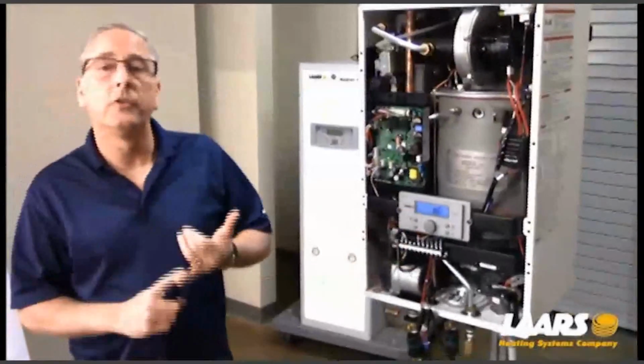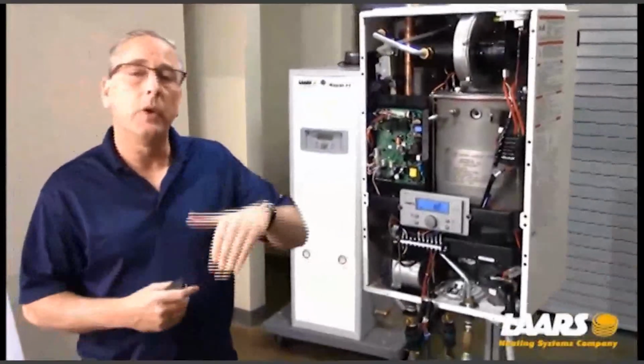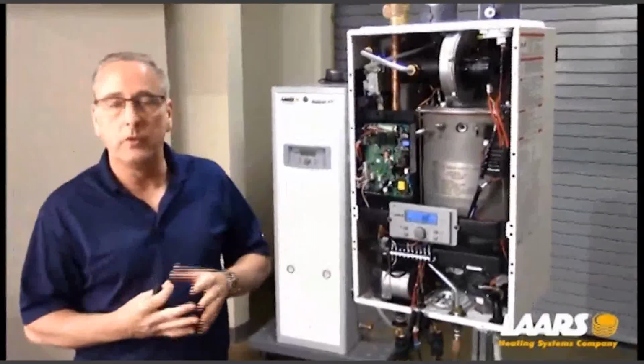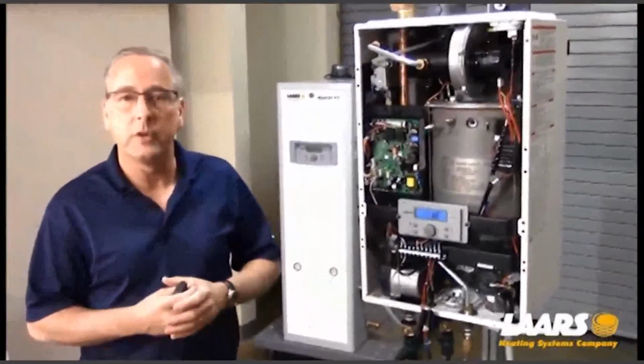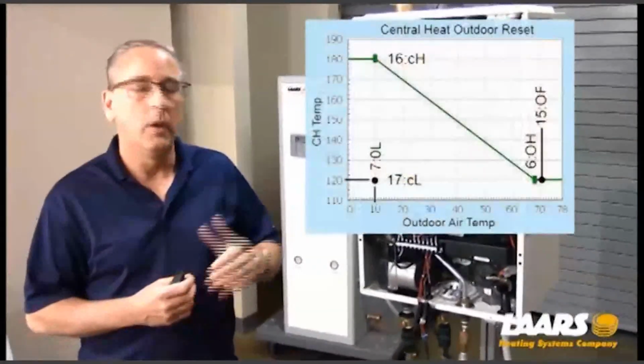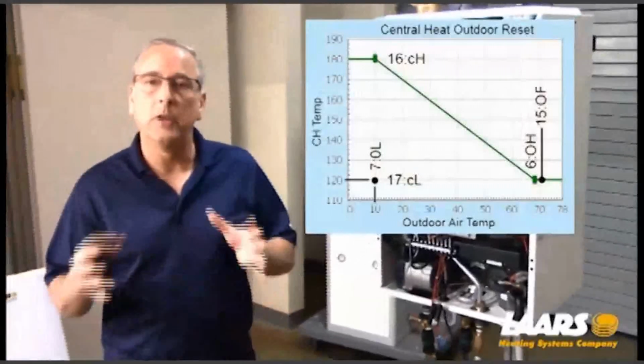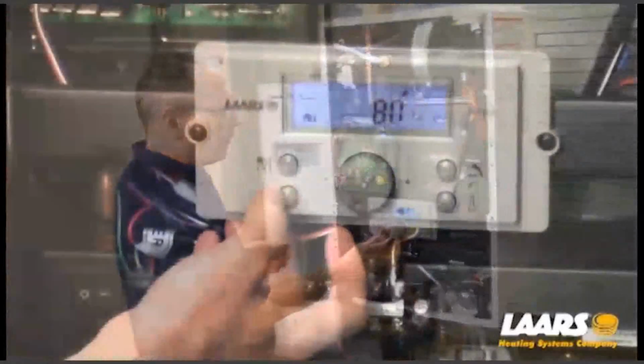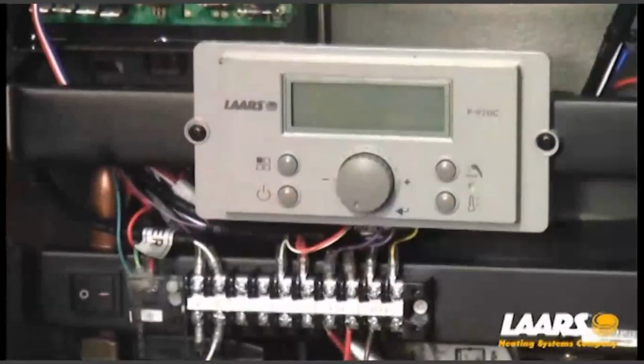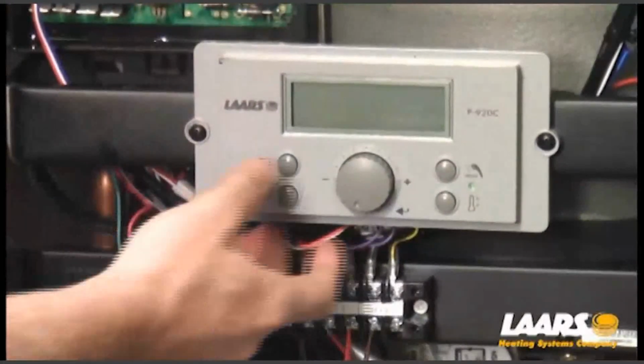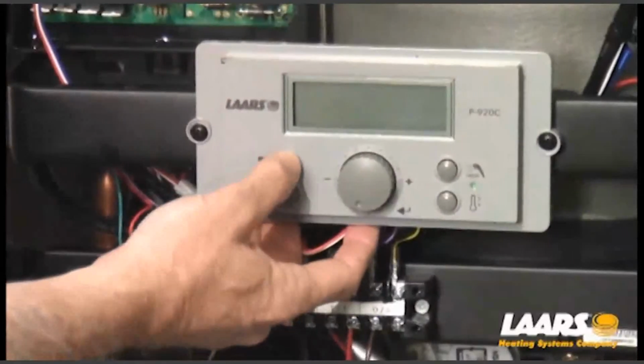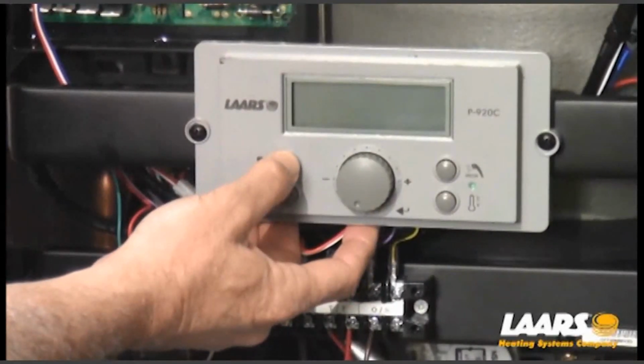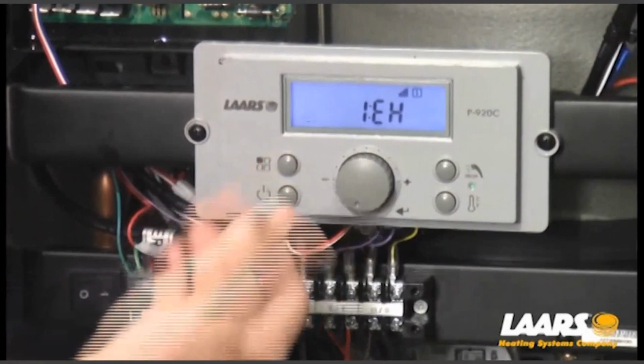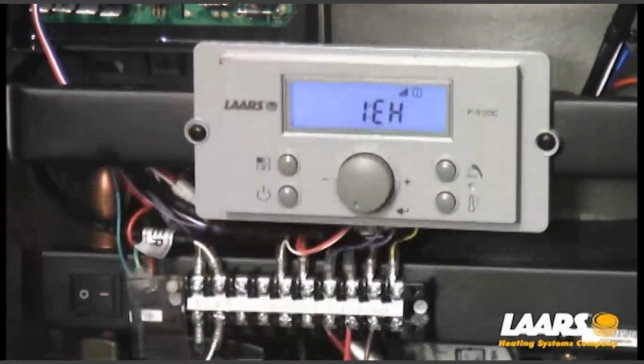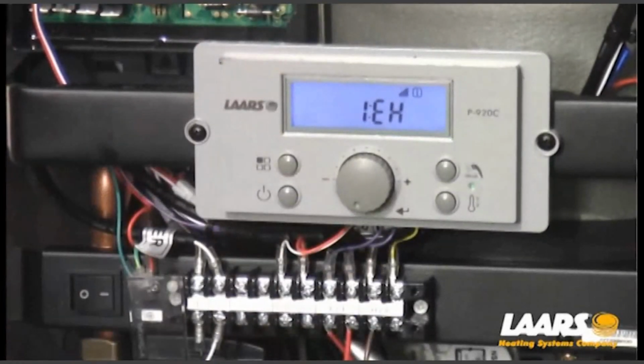Okay, so now that we've set our central heat set point and our domestic set point, we need to get into the installer parameters and adjust our outdoor reset curve. They're already defaulted, so you can customize that to your region. So, very first thing I'm going to do is press the power button and turn the display off. Now I'm going to press and hold the mode button and wait for the screen to liven up. So now 1EH has appeared. I know we're in the installer parameters.